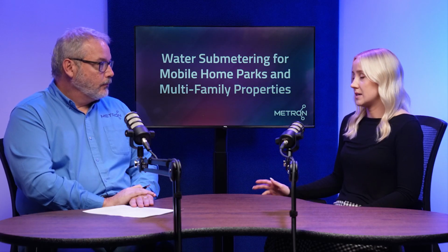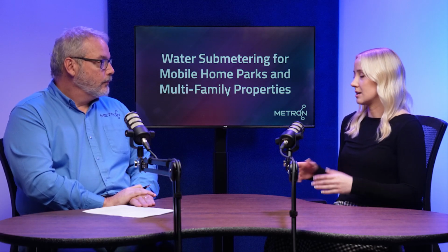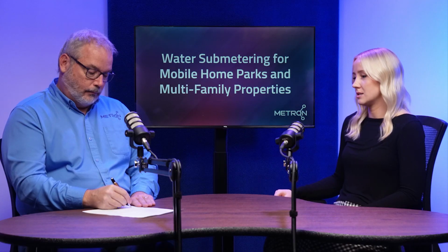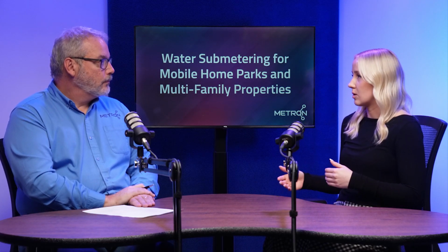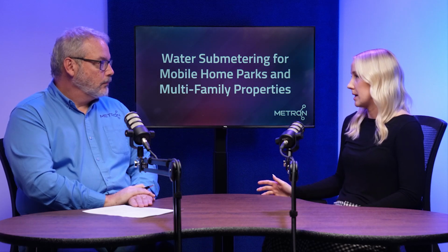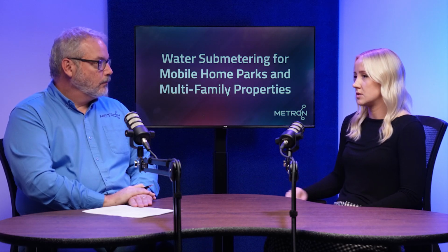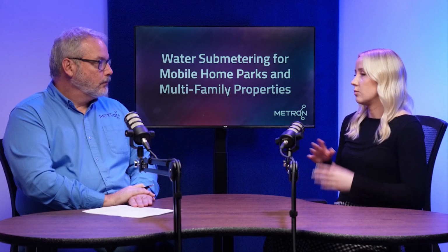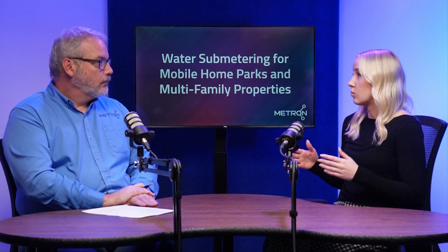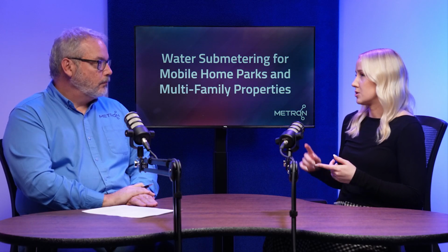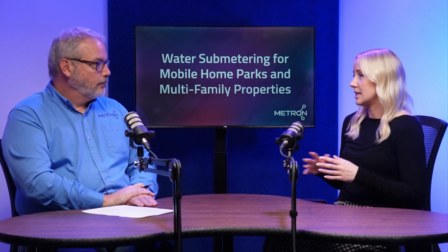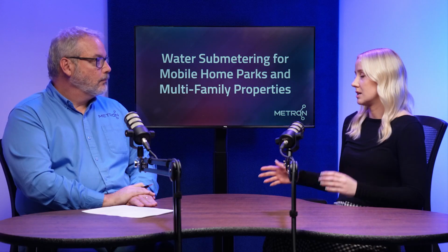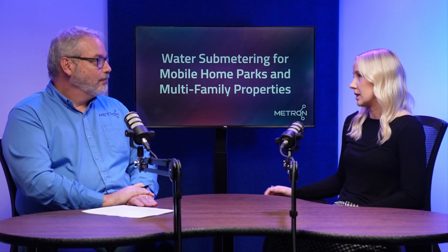Yeah, so there's the obvious, at each meter, there is leak detection. Now, this depends on how often a meter reads. Is it once a day? Is it once an hour? At Metron, we do minute-by-minute analytics. So that gives you spikes of usage, and we can pick up on anomalies, as in when a leak starts, if it's a toilet flapper, a sink that's been left on, anything like that, a pipe that's burst under a unit or in a unit.